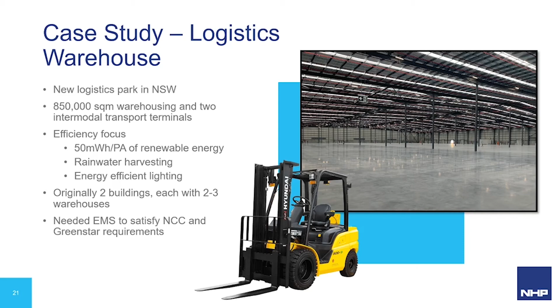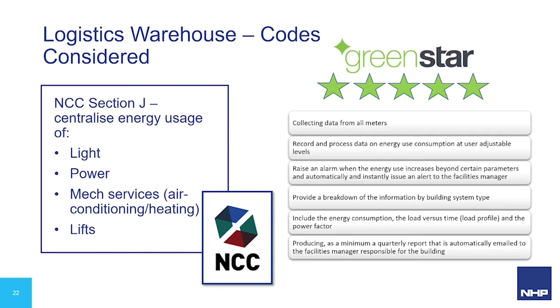As part of NCC Section J, they were required to centralise energy usage of light, power, mechanical services such as air conditioning or heating on site, and lifts. The building owners were also going for a 5-star Green Star rating, which has requirements similar to the NCC, needing to collect data from meters into one place - which made the requirement for an EMS, and in this case a Smart eBOX, for this installation.